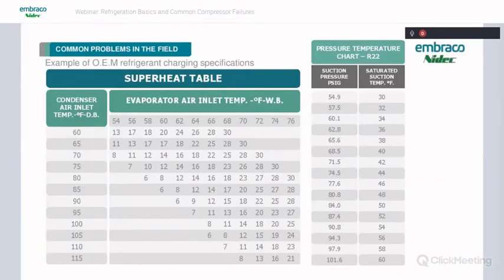So this is an example of a charging chart that a manufacturer might include on an air conditioning condenser. And these are really good to use because on different days, maybe on a cooler day, you can use the parameters on this and get a really good idea of where the charge is at. Some of these require the use of a wet bulb psychrometer or an electronic psychrometer. Some of them you have to plug in wet bulb, but these are a really good idea either on a heat pump or if you're checking an air conditioning system on a cold day.